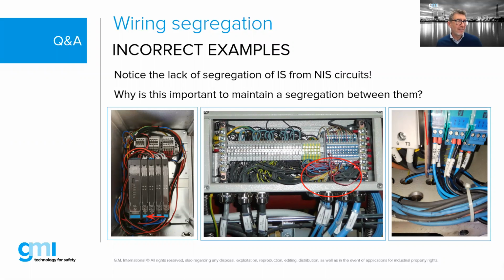Here's a partition. Yeah, that's it right there. They put a partition in, which is great. But then the problem was when they did the installation, they looped those IS cables right next to the power cables. So they have some bundled there, right? That's one issue. And the other issue, if you look at the bottom, it looks like a contactor of some sort with that L1 connection. Right next to it are some conductors leaving, going out to a field device, and we've defeated that 50 mil separation. So that's definitely an issue.